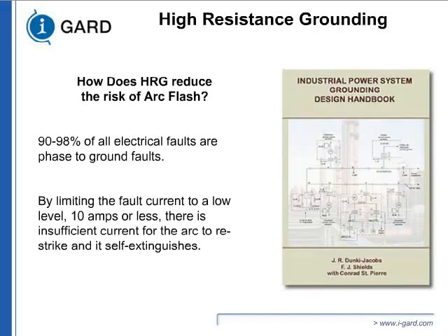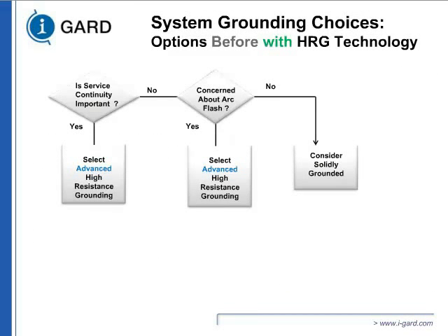Now, what were our options before? When I started designing systems, you only had a few options. If your process continuity was important, use an ungrounded system. If your process continuity was not important, use solid grounded. All of a sudden, high-resistance grounding came in. Now there is no need to have an ungrounded system. If your process continuity is important, you go to advanced high-resistance grounding. So you have all the options that you can pick up: automatic detection, second fault priority. If you're concerned about arc flash, the answer is to go to a high-resistance grounding system.